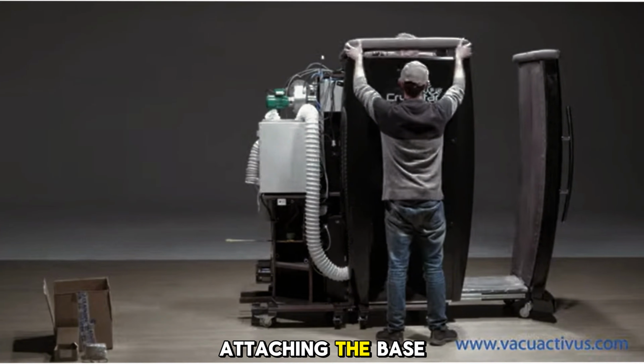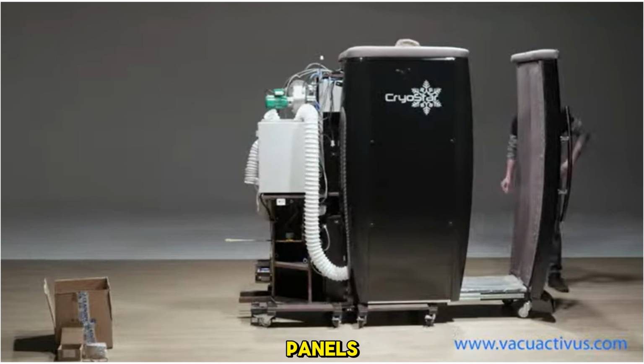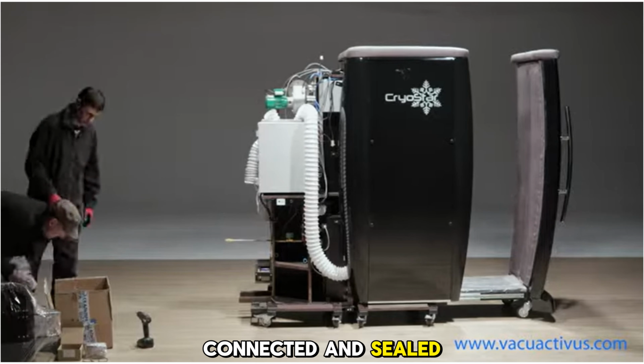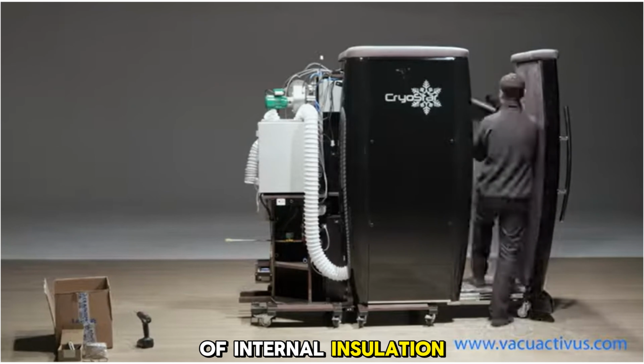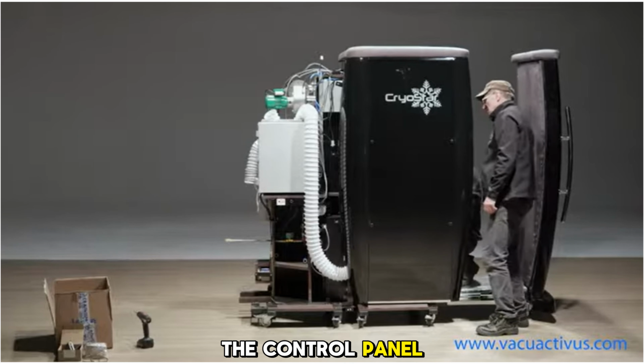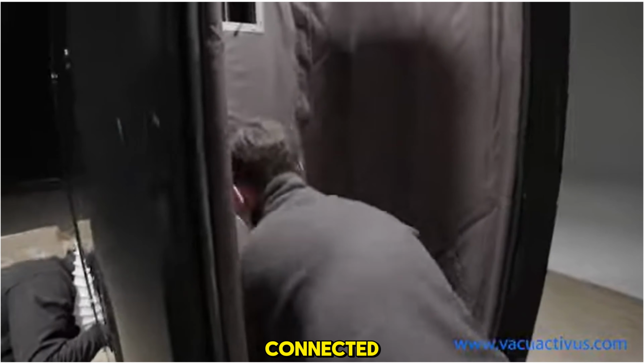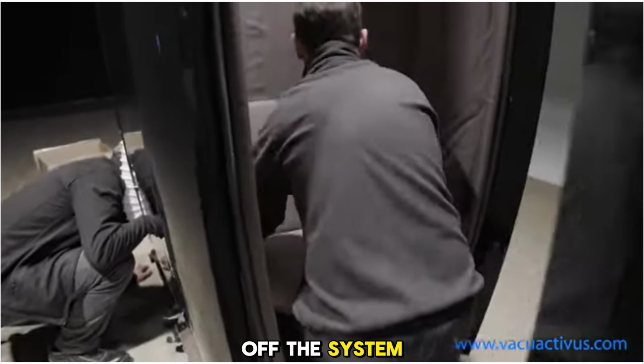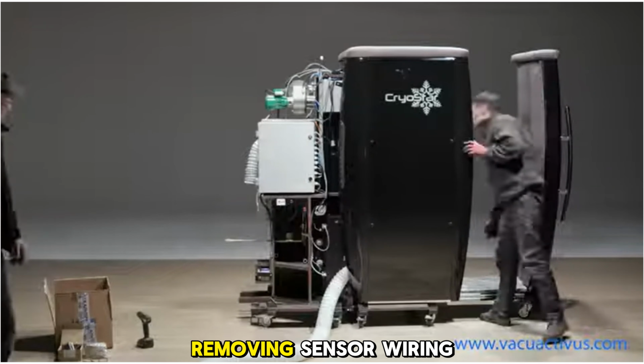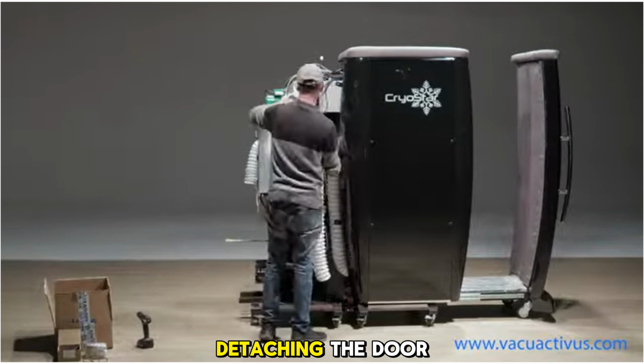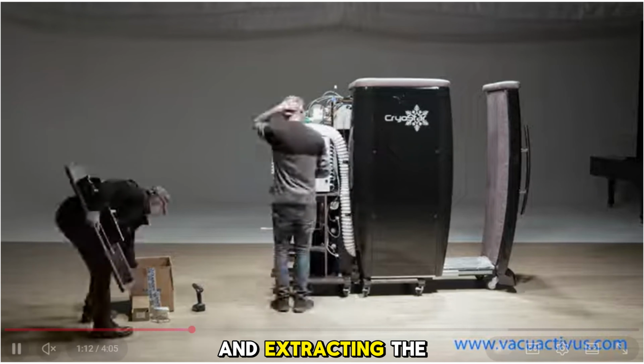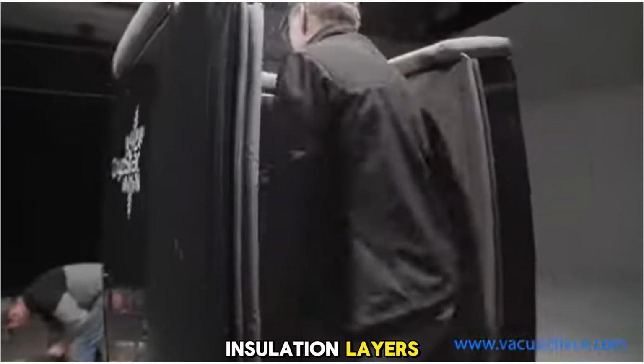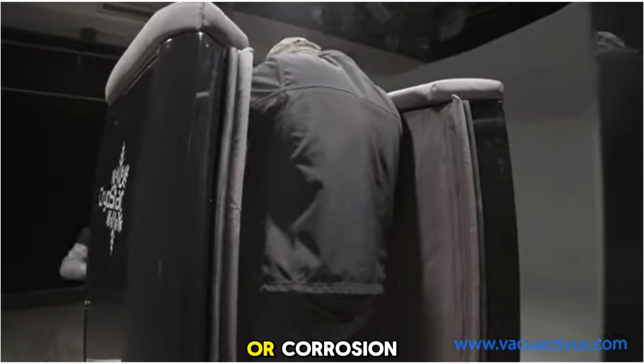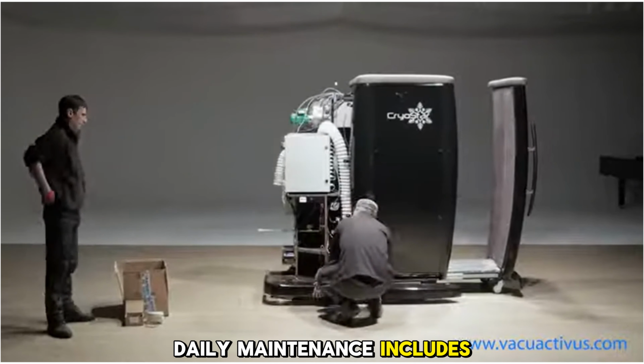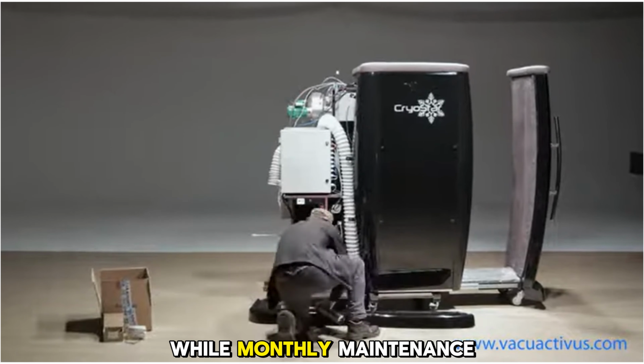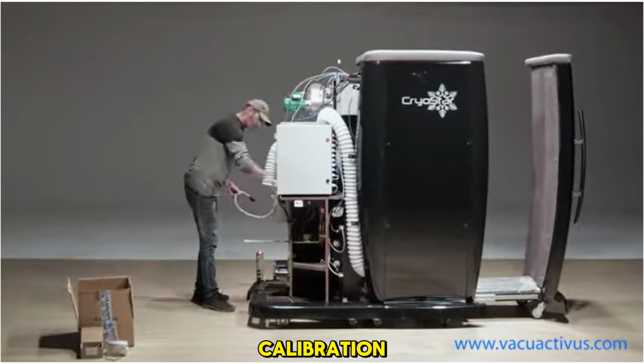Assembly begins by attaching the base platform and securing the outer shell panels. Cooling tubing is connected and sealed, followed by installation of internal insulation and the interior lining. The control panel is mounted and sensor wiring is connected. Disassembly involves powering off the system and venting residual nitrogen vapor, removing sensor wiring and control panel connections, detaching the door and gasket seals, and extracting the cooling tubing and insulation layers. A visual inspection is performed to check for wear or corrosion. Daily maintenance includes checking for frost or moisture buildup, while monthly maintenance involves verifying sensor calibration.